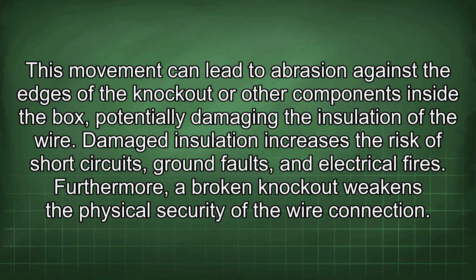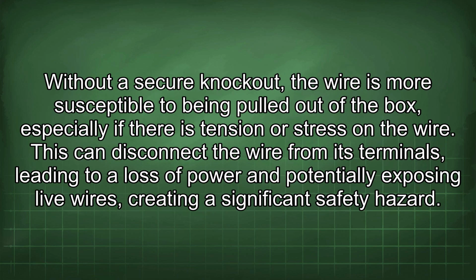Furthermore, a broken knockout weakens the physical security of the wire connection. Without a secure knockout, the wire is more susceptible to being pulled out of the box, especially if there is tension or stress on the wire. This can disconnect the wire from its terminals, leading to a loss of power and potentially exposing live wires, creating a significant safety hazard.